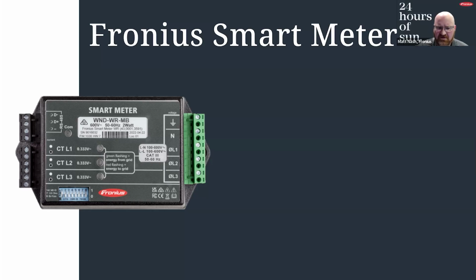So the Up.storage, really the key feature on that is the upgradability of the inverter. So if an installer installs a Gen24 standard grid tie, and later on down the road your customer wants to upgrade with battery storage, they can purchase the upgrade through our web shop and then just add the batteries from there. They do not have to purchase a whole new inverter to do so. And if it's connected to our SolarWeb monitoring portal, it automatically downloads that firmware into the inverter. So at that point, when the installer goes to install the batteries, they just go into the inverter's user interface to turn on the battery backup functionality.